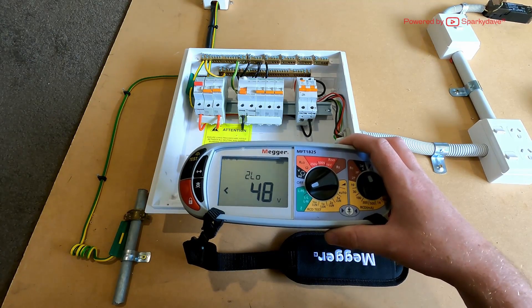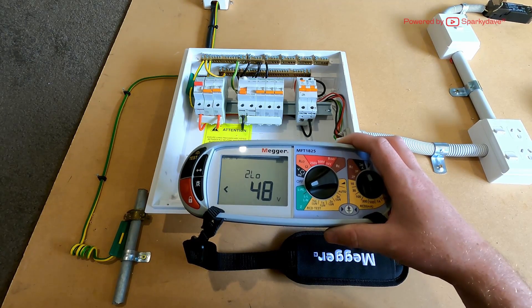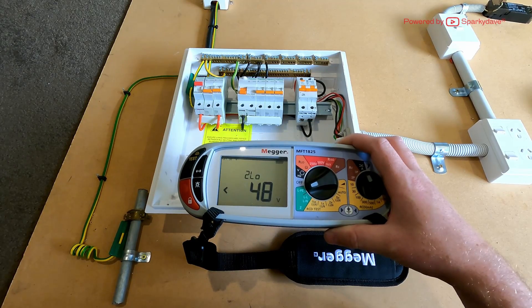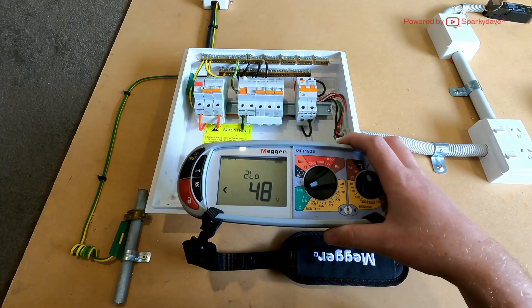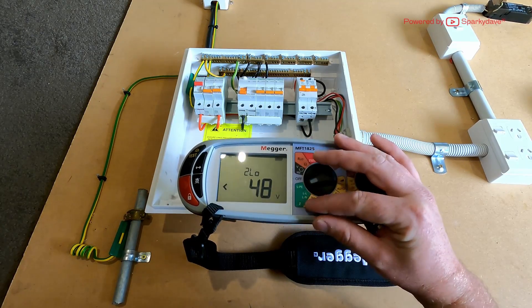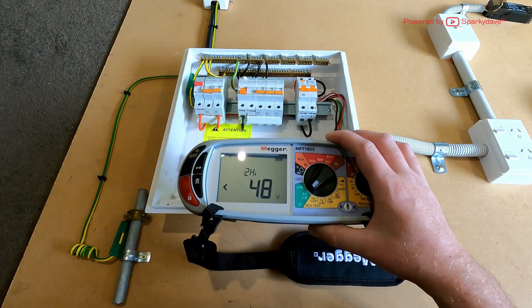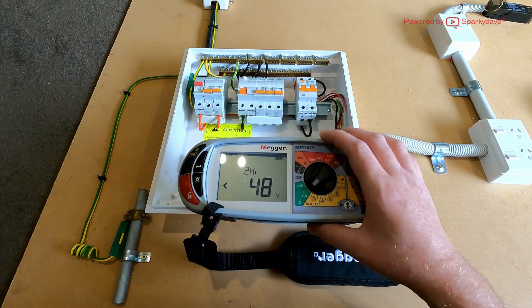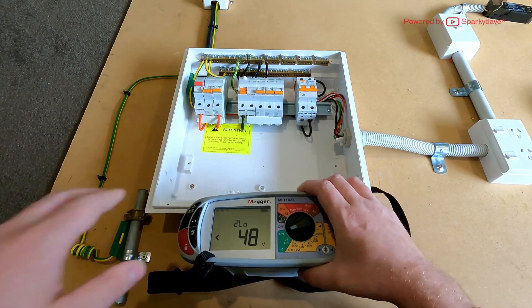The next one is your two low, and you shouldn't really be using this test. What it's designed for is if you've only got phase earth available and you need to do a low current test somewhere. On here, flick it to line neutral. The only test available is your two lead high current test.